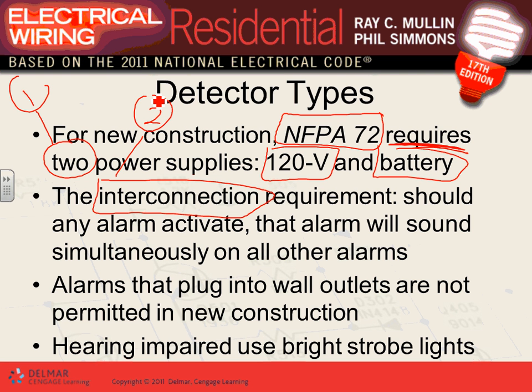Plug-in ones are not permitted. You cannot plug them in. In old construction, remodeling, they allow you to plug them in as smoke detectors, but not in new construction. You can't plug them in.